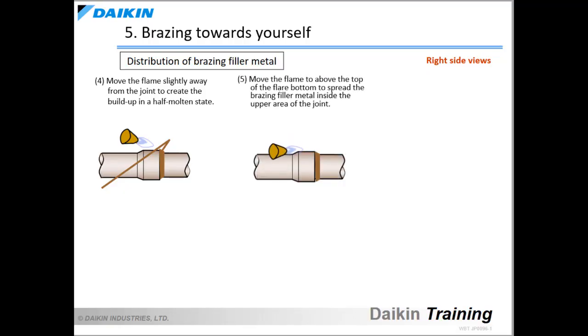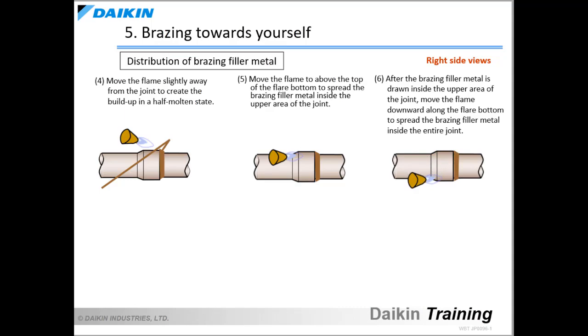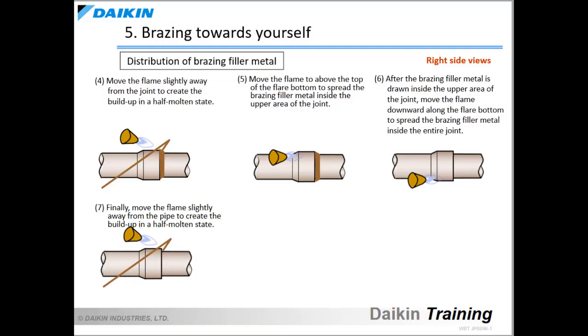Next, move the flame to the top of the flare bottom to spread the brazing filler metal inside the upper area of the joint. Then, move the flame downward along the flare bottom to spread the brazing filler metal inside the entire joint. At this time, you can see that the brazing filler metal build-up on the flare end is reducing, and it is being drawn inside the joint. Immediately after confirming that the build-up is reducing as it is drawn inside the joint, move the flame to the upper area of the inner pipe and slightly away from it to create the brazing filler metal build-up in a half-molten state. Finally, check the entire circumference of the brazing area, and if there is any insufficiency, add more brazing filler metal.